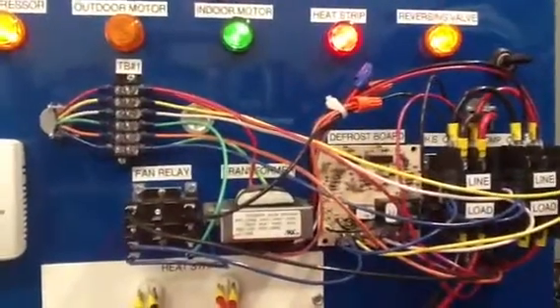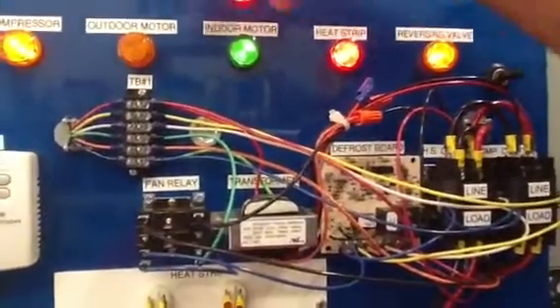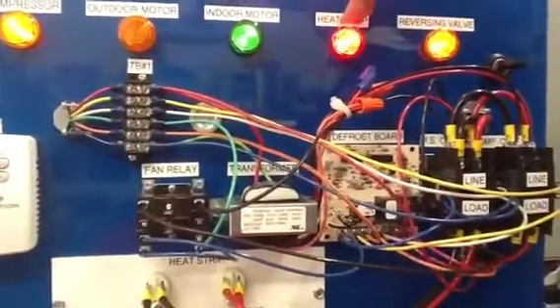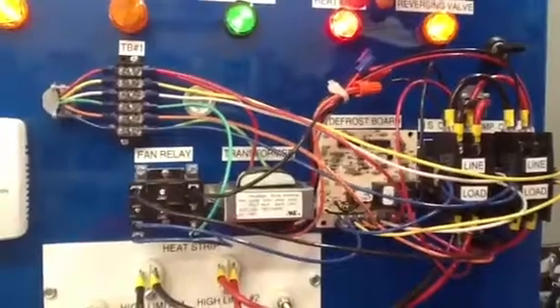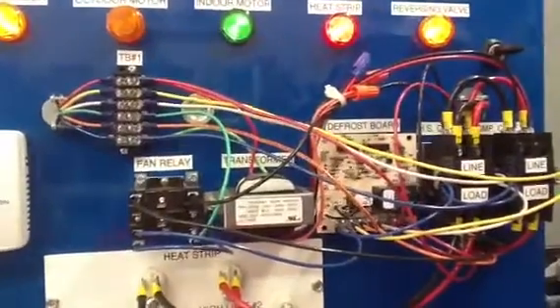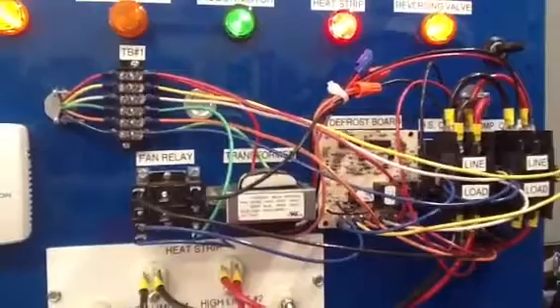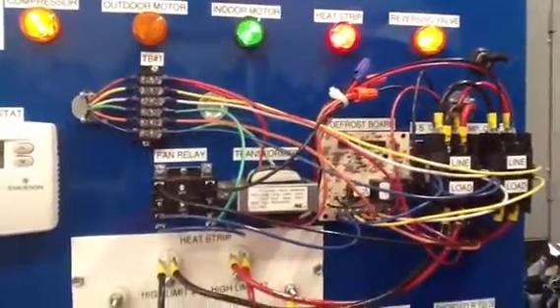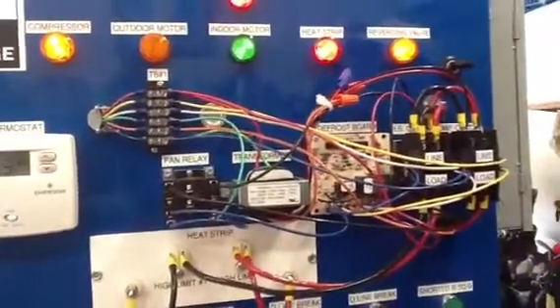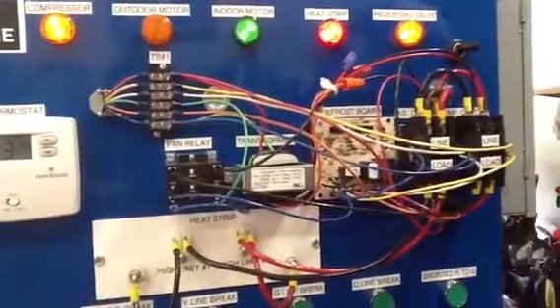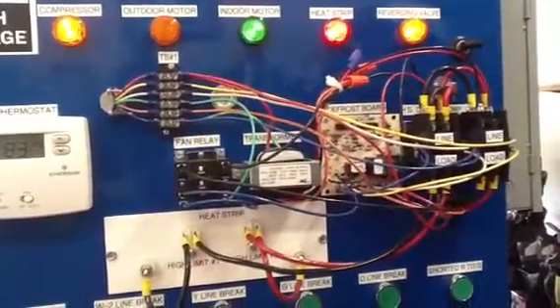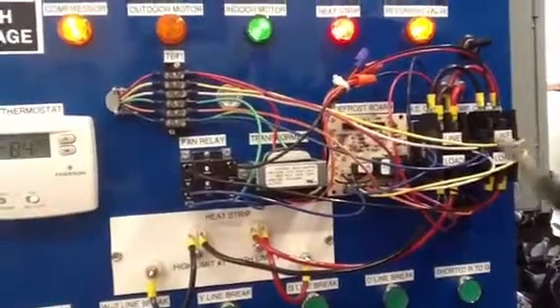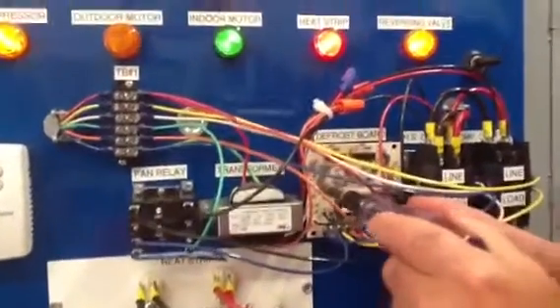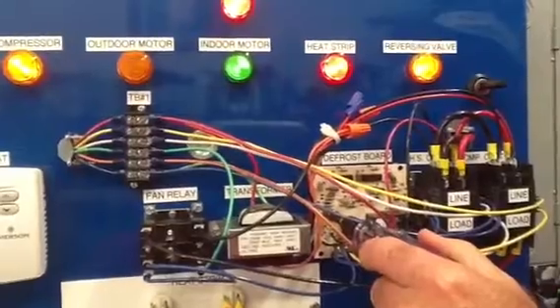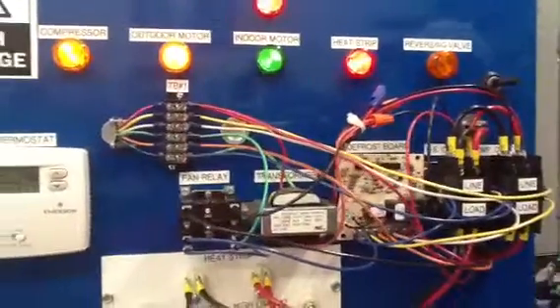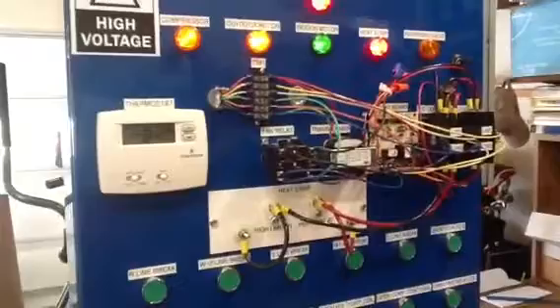And defrost is initiated. Reversing valve is energized. Outdoor motor is shut off. Heat strip will stay running because it was in a heat call already, a two-stage heat call. Now the defrost board will stay in the defrost mode for 10 minutes or until the defrost thermostat opens, whichever comes first, and we are electrically manipulating that defrost thermostat, so we will have to terminate defrost manually. And you terminate defrost. Now we are back into a two-stage heat call, and everything is working properly.